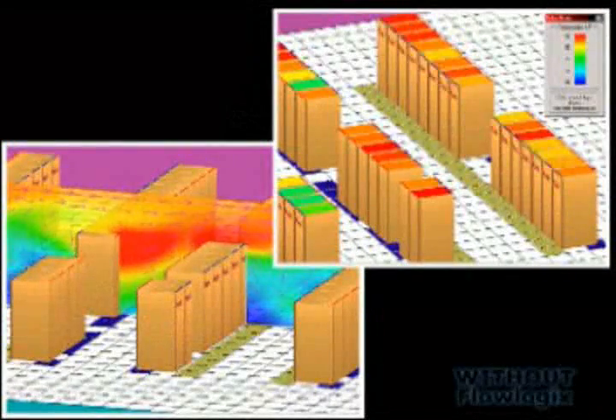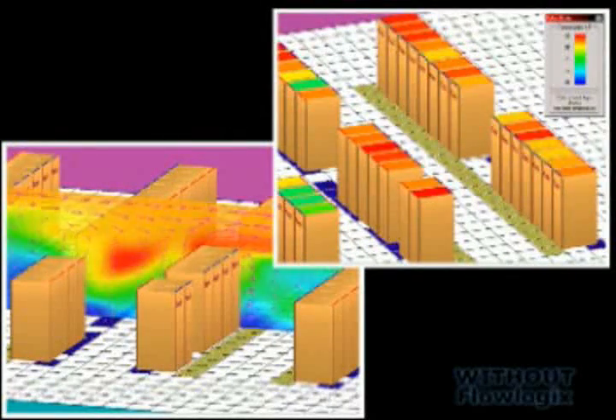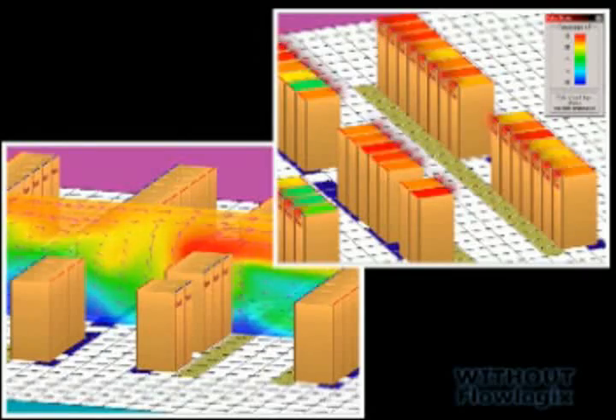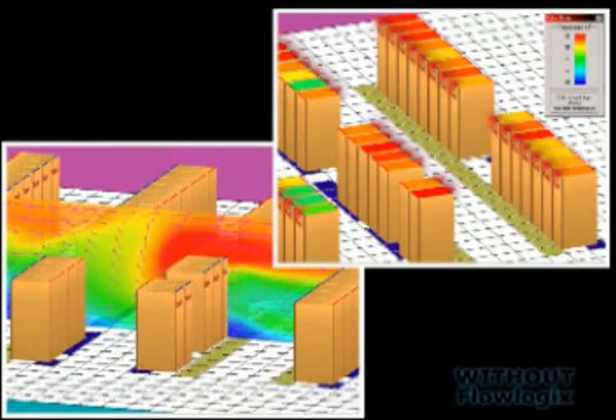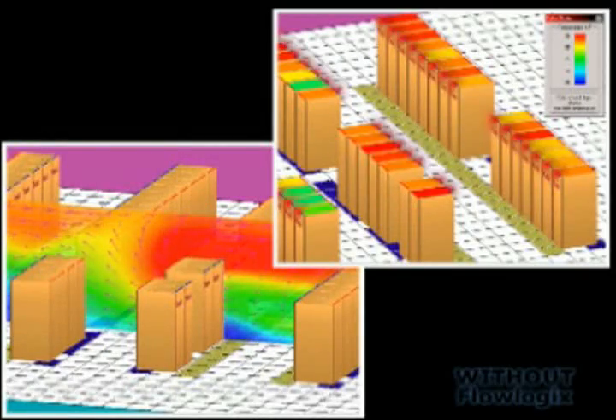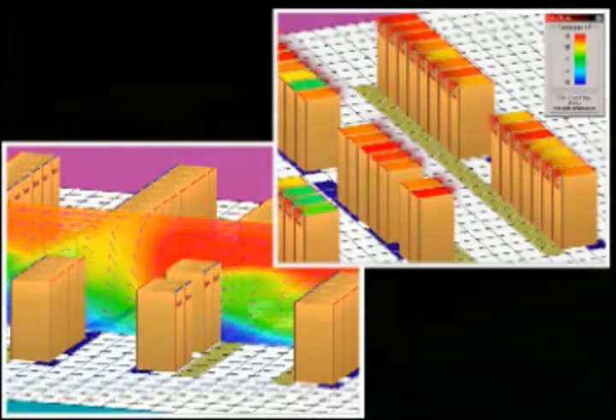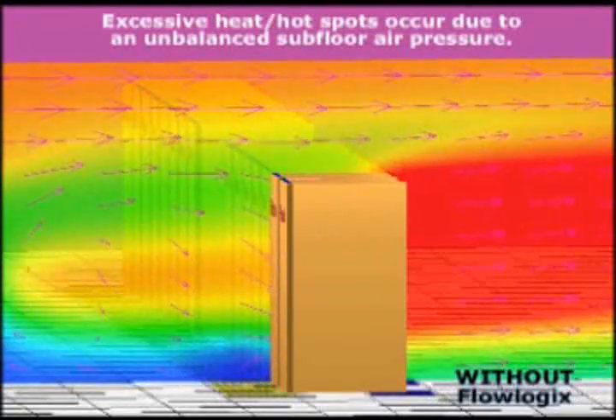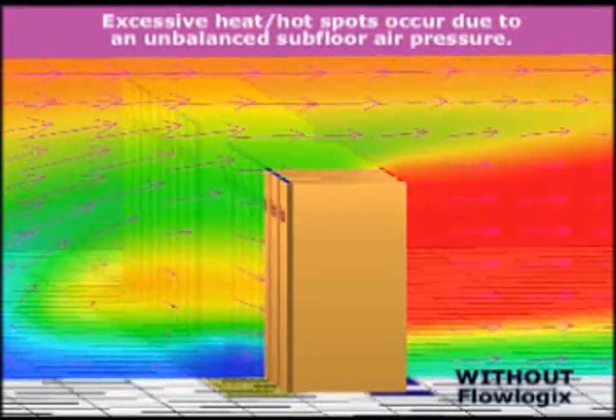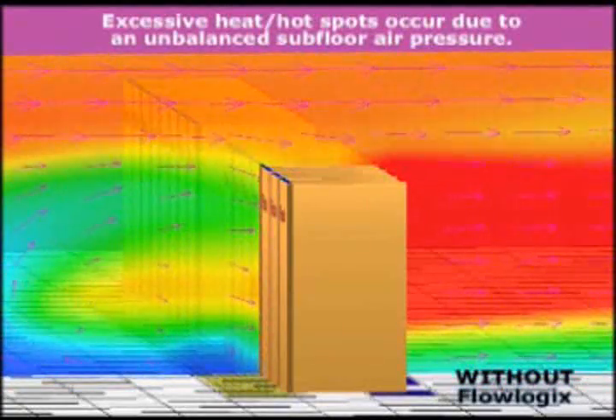Excessive heat in hotspots can produce damaging effects within a data center and lead to server and equipment failure. These problems are rarely due to a lack of cooling capacity. Rather, they are caused from a lack of proper air flow management.